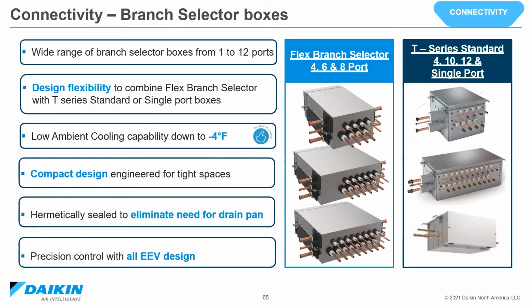Compatible with all the Daikin Branch Selector boxes, the Emerion's perfect for simultaneous heating and cooling designs. Here you can see the single port through the 12 port options. And it also includes the new flex boxes that allow for a 9-inch ceiling cavity. As architects continue to reduce mechanical space in the building, it's important to be able to offer them a branch selector box that is less than 9 inches and a ducted fan coil that is less than 9 inches to maximize the applicable space in the building and minimize mechanical space.